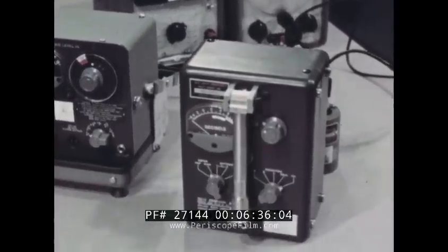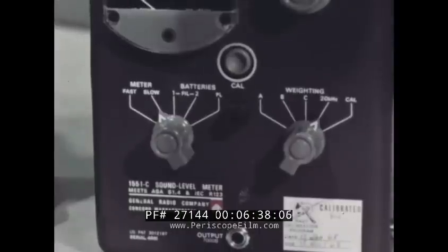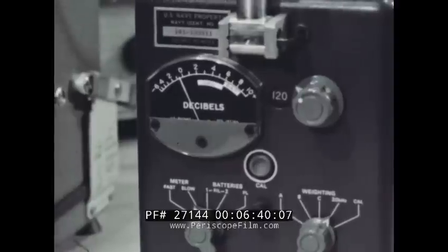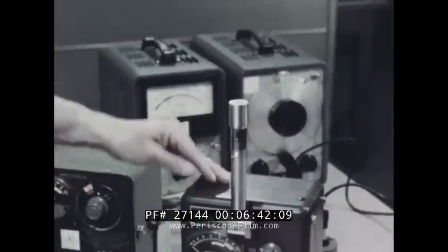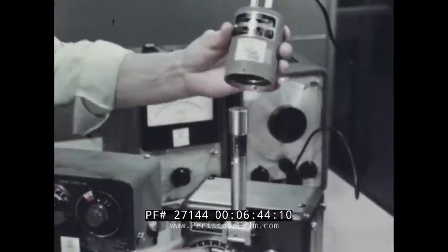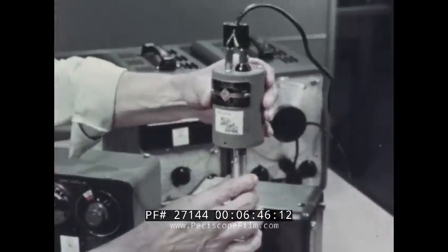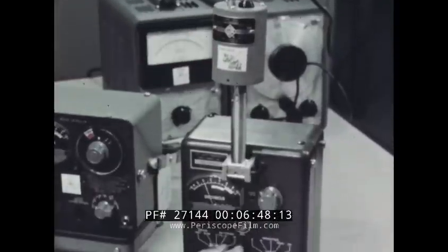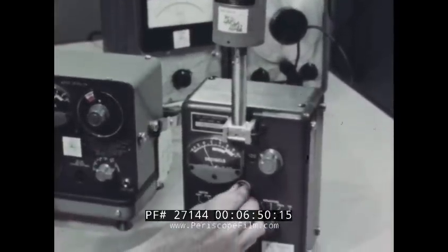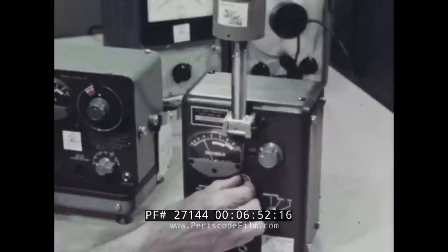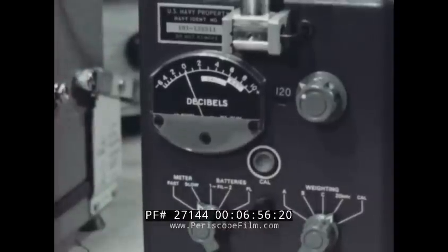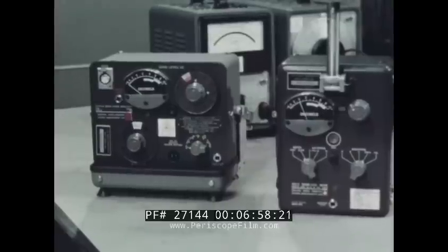On the sound level meter, the weighting switch has been set to 20 kc and the attenuator switch to 120. Put the calibrator firmly on top of the mic to feed in the signal and read the meter. It should be within 1 dB of 0. If not, adjust with the thumbset control. The sound level meter is now ready.